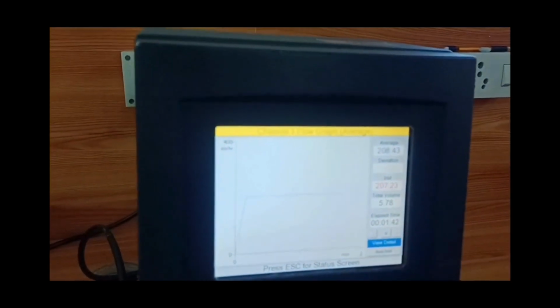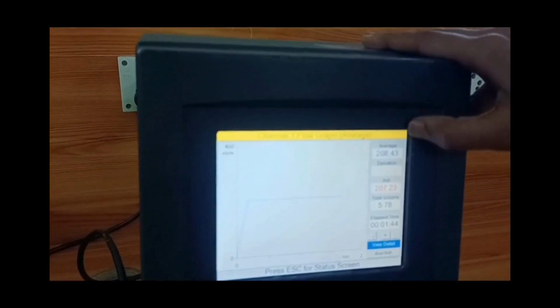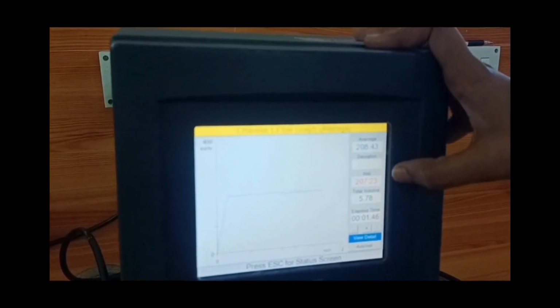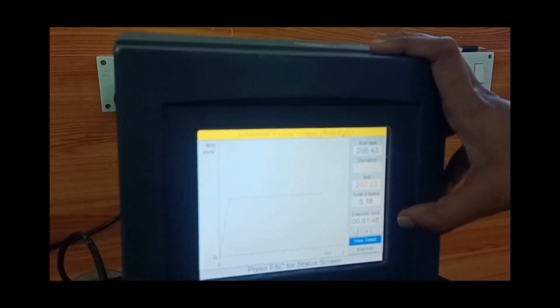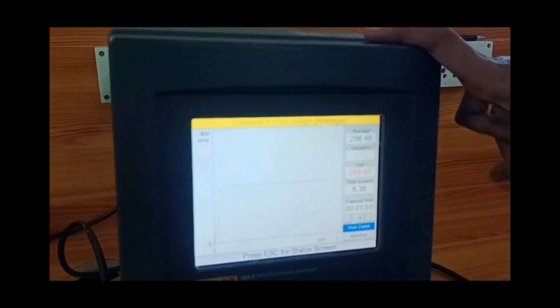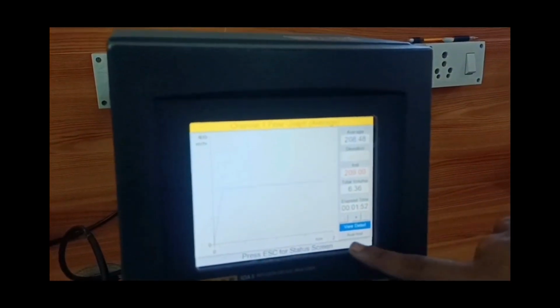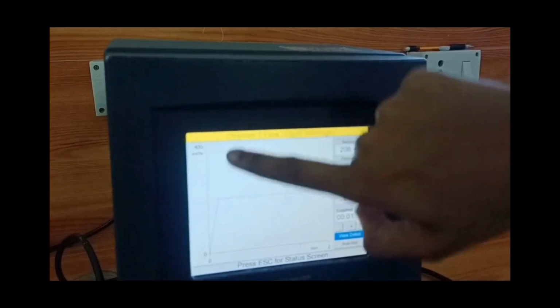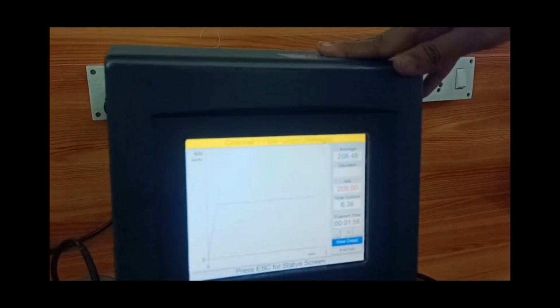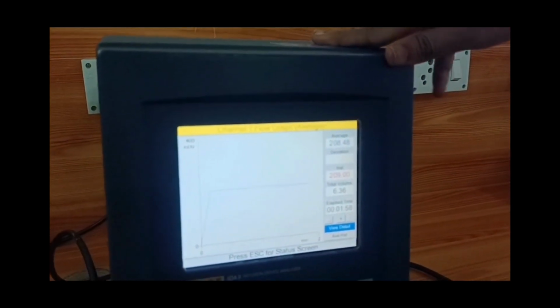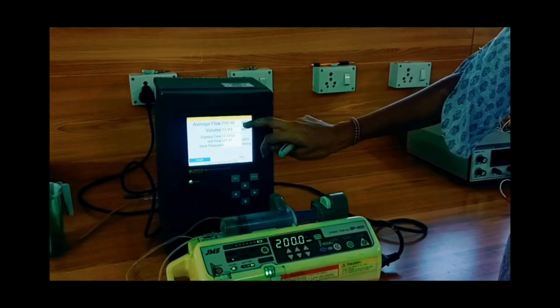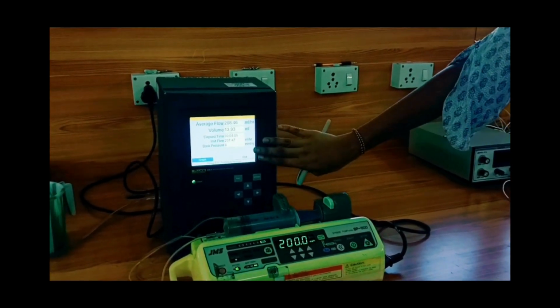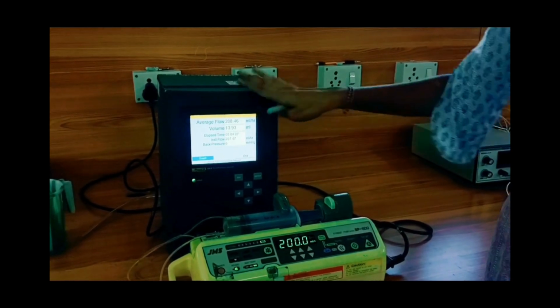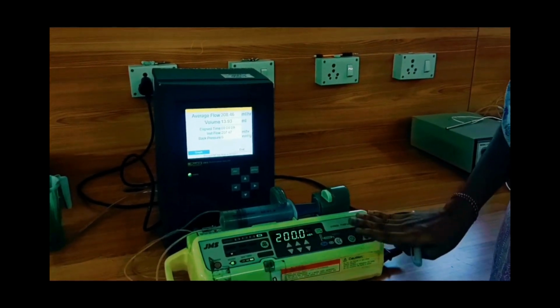This is the graph. Same as before, the average flow, the instantaneous flow, the total volume, the elapsed time. The x-axis indicates the time and the y-axis indicates the ml per hour. These two values are matching with plus or minus 5 error in the infusion device analyzer. From this we can say that the syringe pump is calibrated.